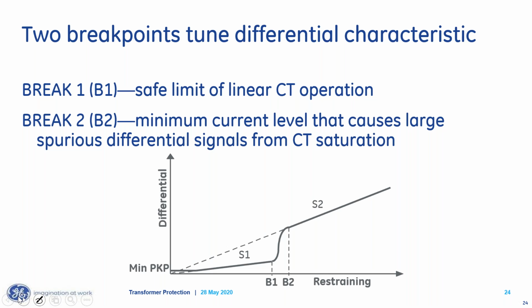That's for most differentials. That's for differentials on transformers or stators, motors, or generators, buses, things of that nature. I could feel comfortable setting that as low as 20%. Transformers are a different thing because I've also got to accommodate some error associated with the transformer itself, right? I'll have no load losses in that transformer. Those no load losses can account for some error.